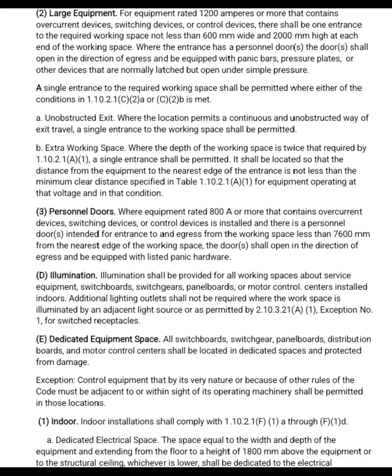It shall be located so that the distance from the equipment to the nearest edge of the entrance is not less than the minimum clear distance specified in Table 1.10.2.1 A1 for equipment operating at voltage in that condition. Number 3. Personnel doors. Where equipment rated 800 A or more that contains overcurrent devices, switching devices, or control devices is installed and there are personnel doors intended for entrance to and egress from the working space less than 7,600 mm from the nearest edge of the working space, the door shall open in the direction of egress and be equipped with listed panic hardware.